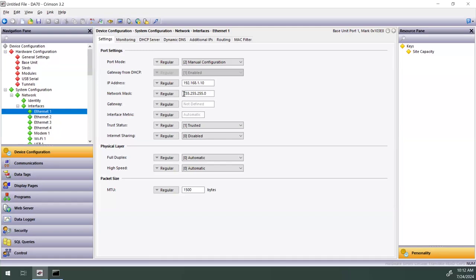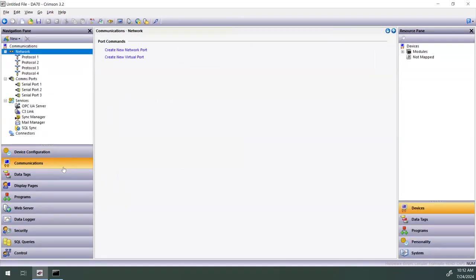So next I'm going to move straight to the Modbus device configuration. So I'll navigate to the communications category and add my Modbus device. As I mentioned earlier, this is a serial Modbus RS485 device, and it's connected to serial port 2 on my DA70. So I'll click on serial port 2.